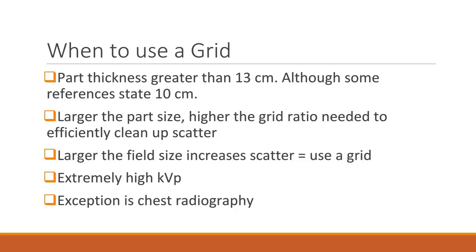Whether in the table Bucky, upright Bucky, or attached to an image receptor, grids should be utilized when part thickness is greater than 13 centimeters. However, some older references state part thicknesses greater than 10 centimeters require a grid. As the part thickness increases, the grid ratio utilized should also increase. Large field sizes, such as 14 by 17 inches, may require a grid even if the part is less than 13 centimeters, because larger field size means there is more tissue being exposed. It is more spread out rather than stacked, but causes scatter nonetheless, and a grid will need to be employed to clean up the scatter and restore the contrast of the resulting image.